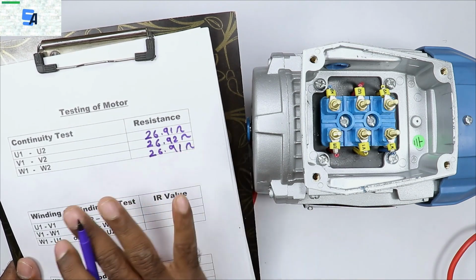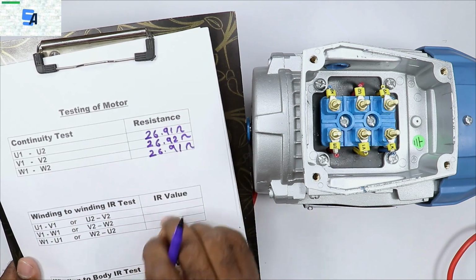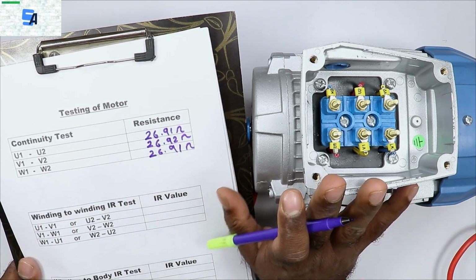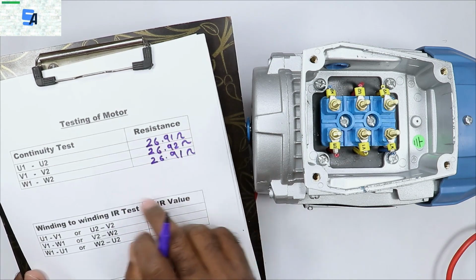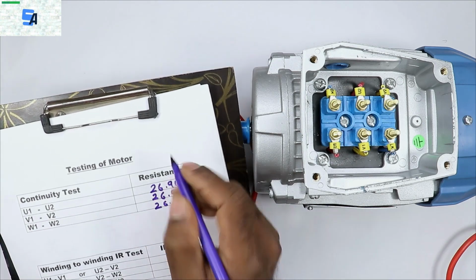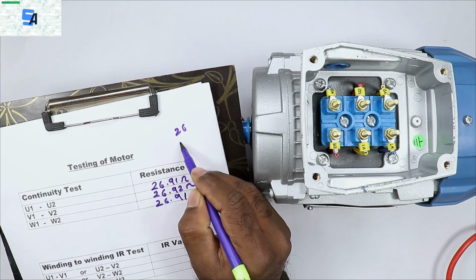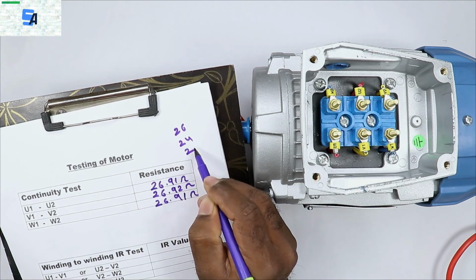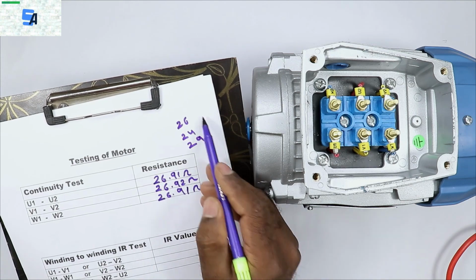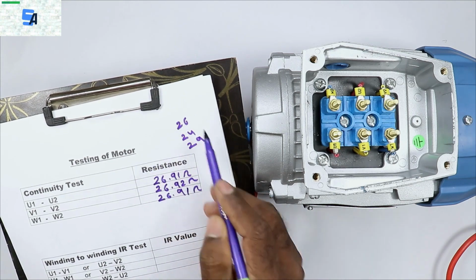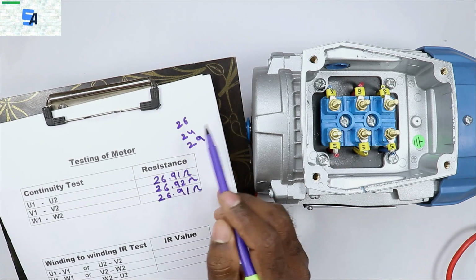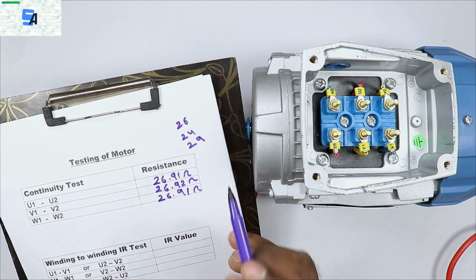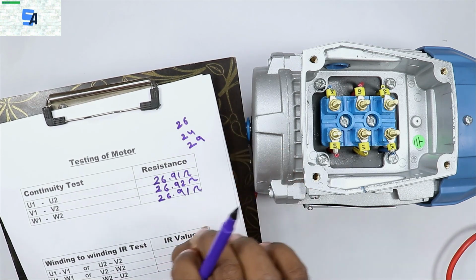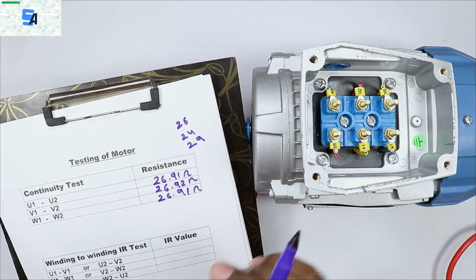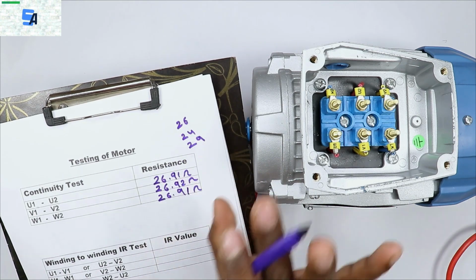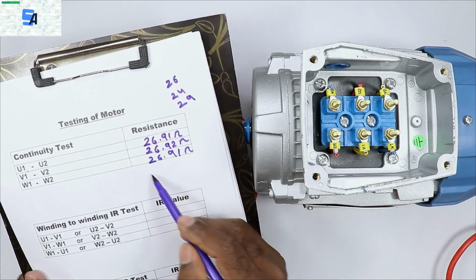If the resistance of your motor is balanced, I mean the values are the same, then in this condition there is no problem in the winding of the motor. Now apart from these values, suppose you get resistance values of 26 ohm, 24 ohm and here you get 29 ohm. If it shows unbalanced resistance like this, I mean there is a difference in the resistance values, then in this condition you can say there is some problem in the winding of the motor due to which the resistance got unbalanced. So the resistance of your motor must always be balanced.